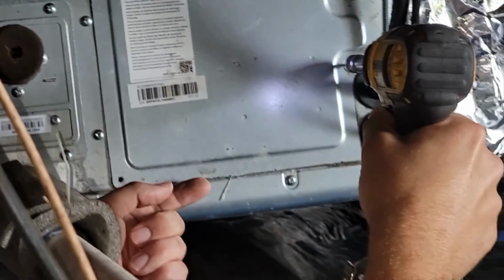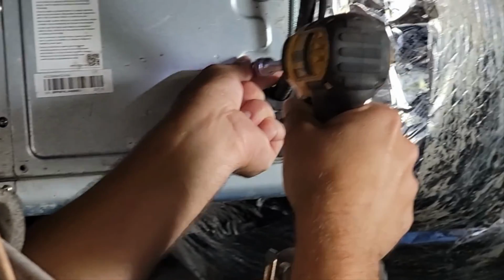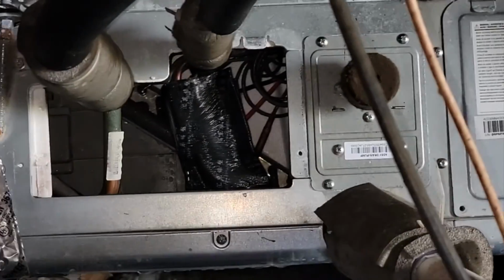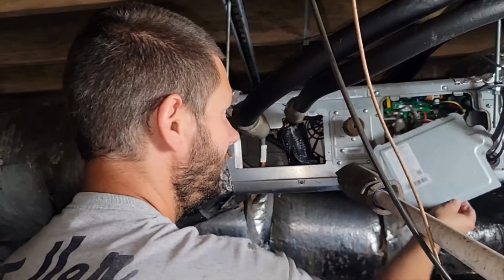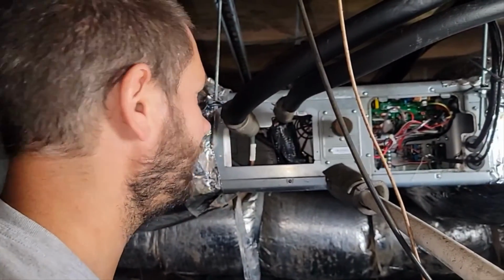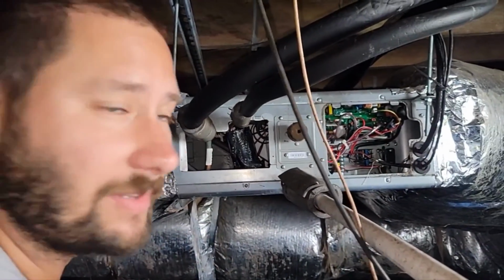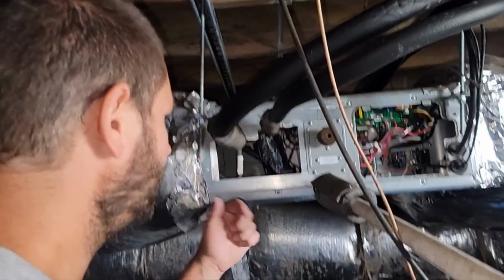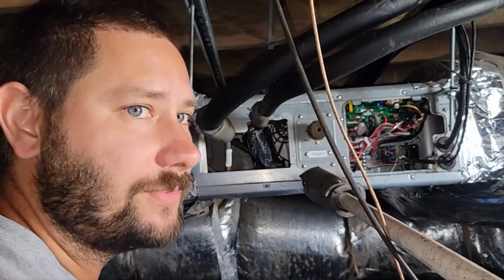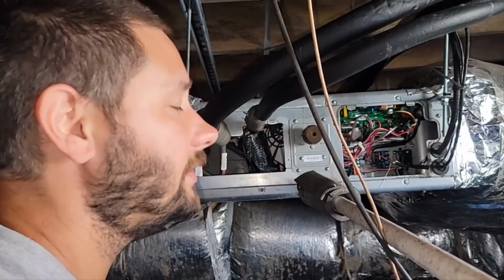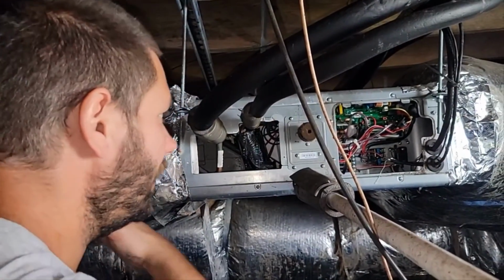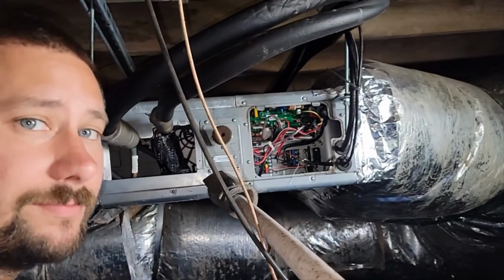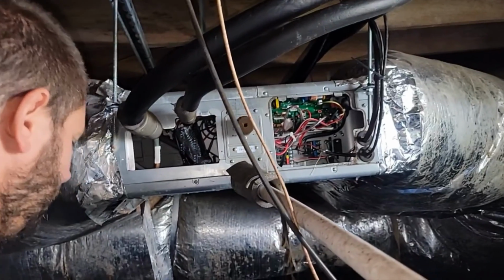If this equipment is not installed properly, meaning there's not enough clearance for serviceability, it can be a nightmare getting to these sensors. I've had to take the ductwork off, the top panel off, or the bottom panel off just to get to the sensors, and it can be a total headache. So this one's going to be pretty easy, and I'm really glad.